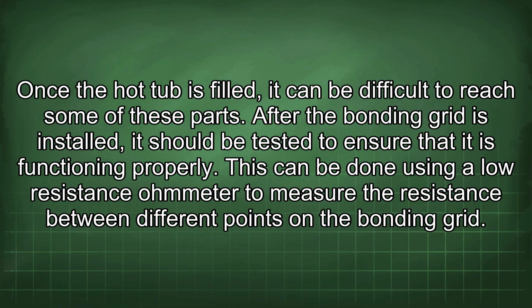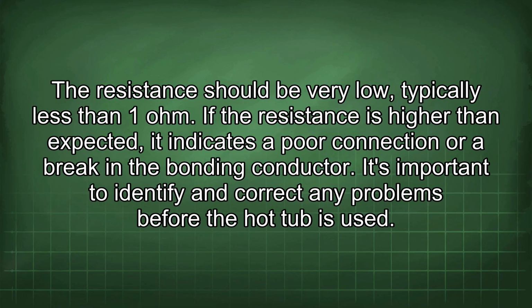After the bonding grid is installed, it should be tested to ensure that it is functioning properly. This can be done using a low resistance ohmmeter to measure the resistance between different points on the bonding grid. The resistance should be very low, typically less than 1 ohm. If the resistance is higher than expected, it indicates a poor connection or a break in the bonding conductor. It's important to identify and correct any problems before the hot tub is used.